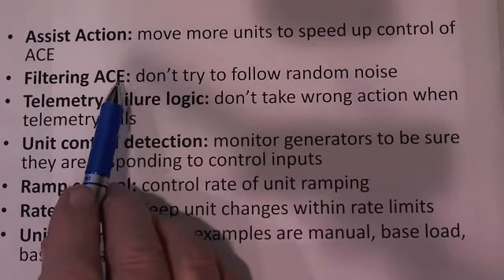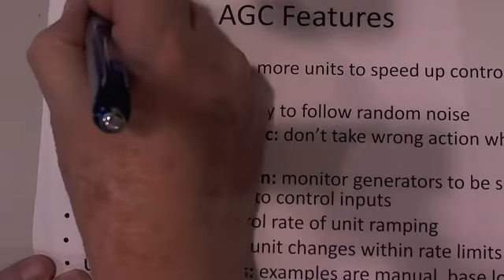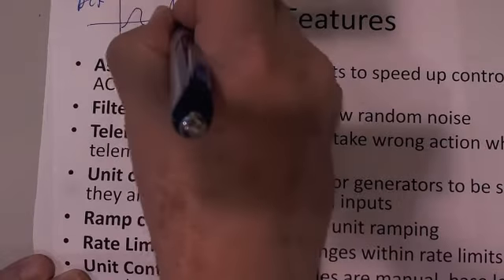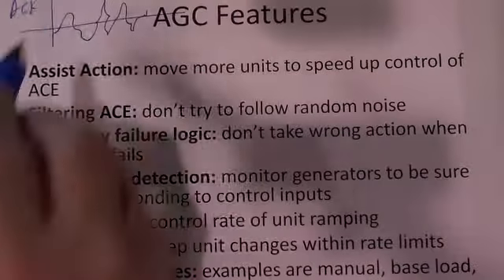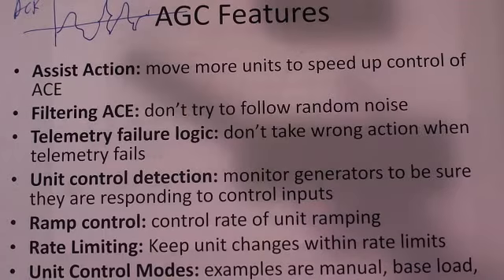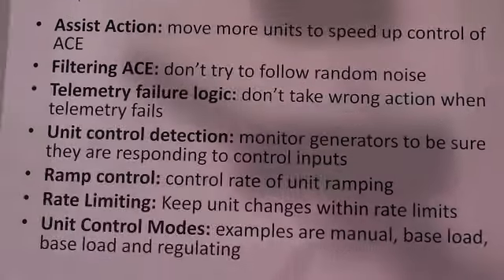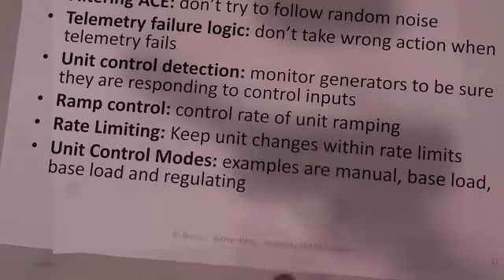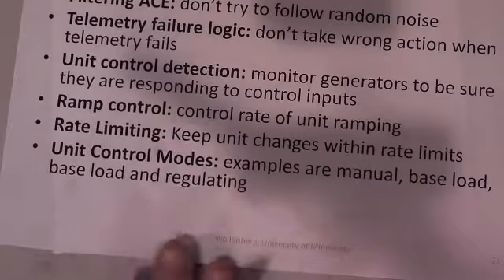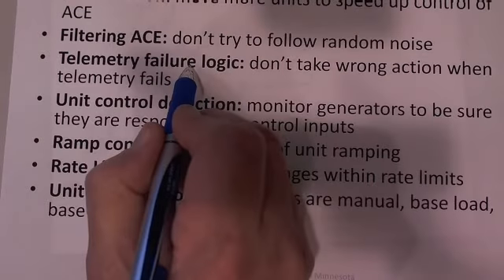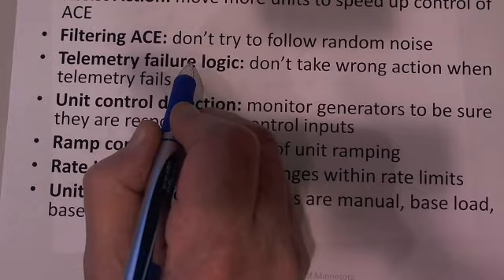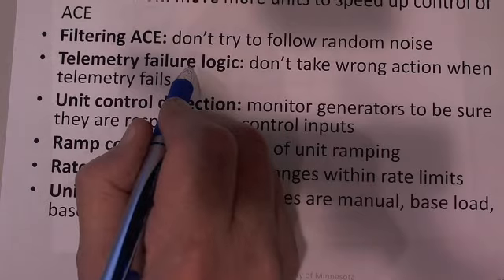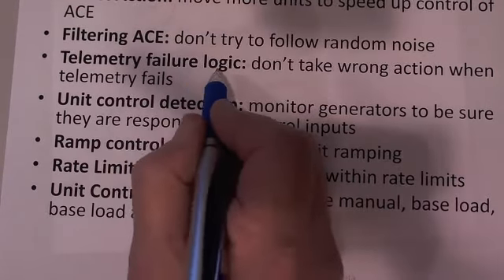So we'd like to know, is the ACE a signal that's jumping around like this, and if it's just oscillating, set your generation to operate along the average, but you can filter it to try to get the oscillating parts of it out of there. If there's a telemetry failure, then you want to turn part of the control system off, not the whole thing, so that the telemetry failure says, I'm not getting through to one of the generators. Well, then don't try to keep raising it up, because it's not going to get the signal.